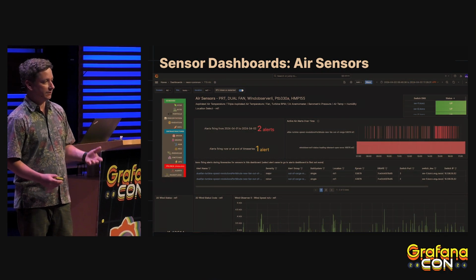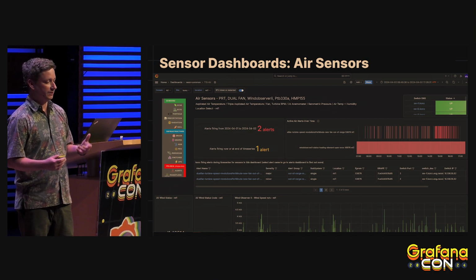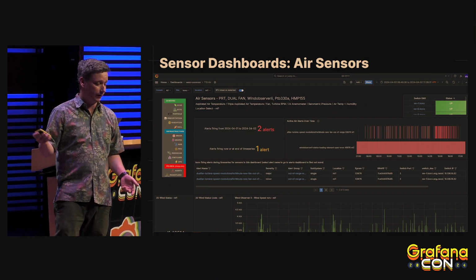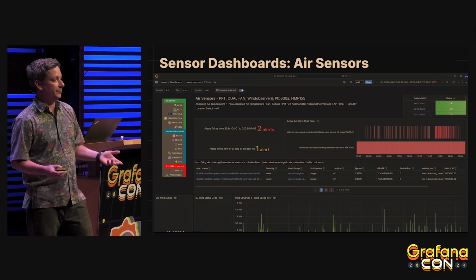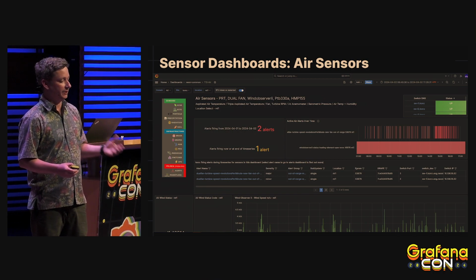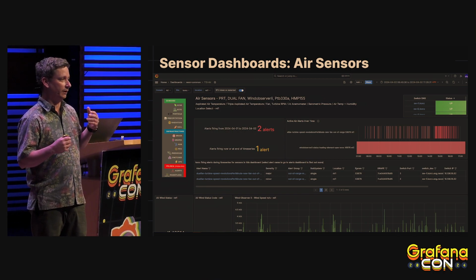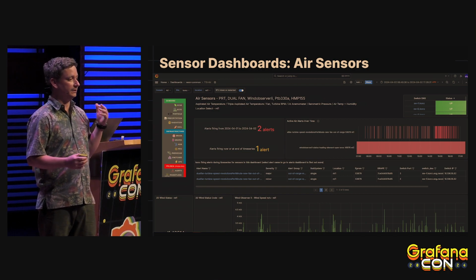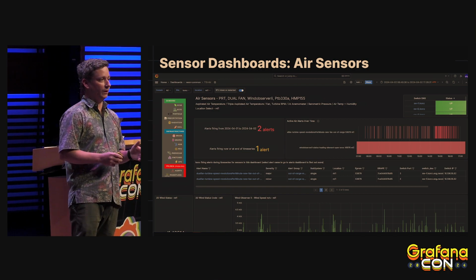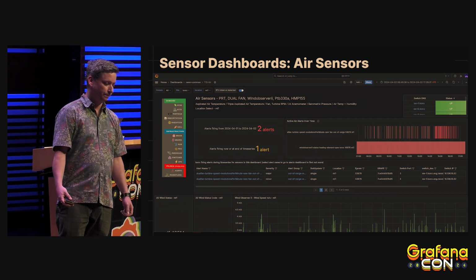You might notice that this alert changes in severity over time. It's kind of slight, but it changes color there. We found that pending time intervals on alerts often missed intermittent failures, so instead we applied a percentage over time, usually around 10% on the hour, before escalating the severity on an alert.